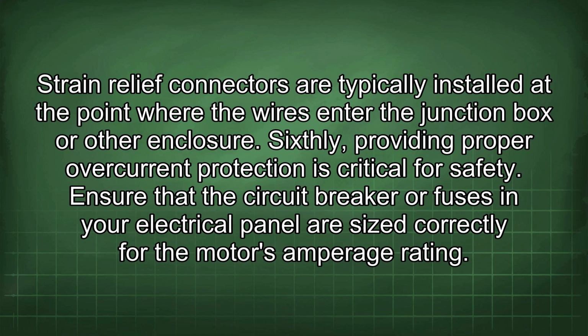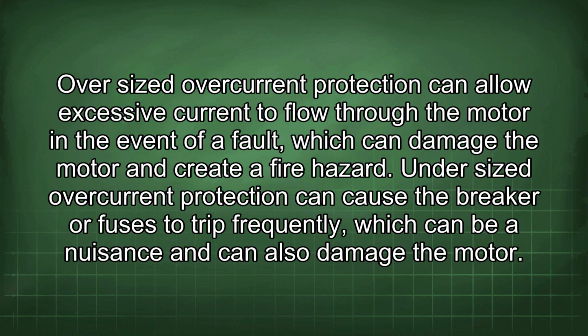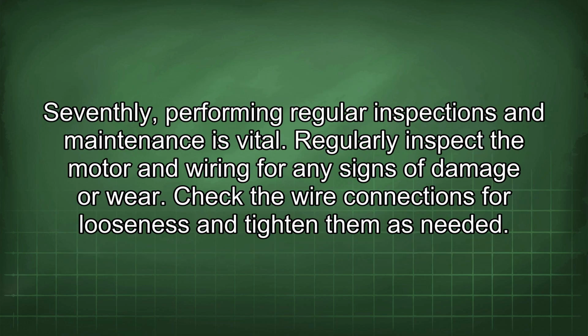Sixthly, providing proper overcurrent protection is critical for safety. Ensure that the circuit breaker or fuses in your electrical panel are sized correctly for the motor's amperage rating. Oversized overcurrent protection can allow excessive current to flow through the motor in the event of a fault, which can damage the motor and create a fire hazard. Undersized overcurrent protection can cause the breaker or fuses to trip frequently, which can be a nuisance and can also damage the motor.